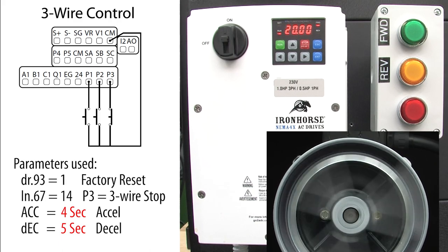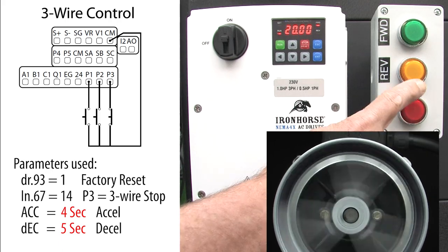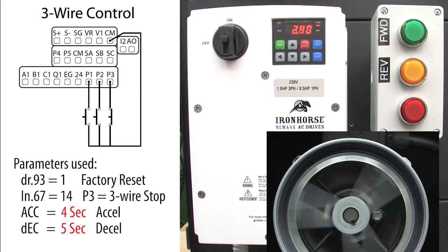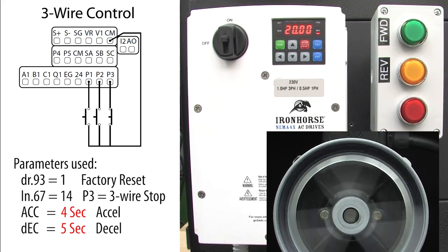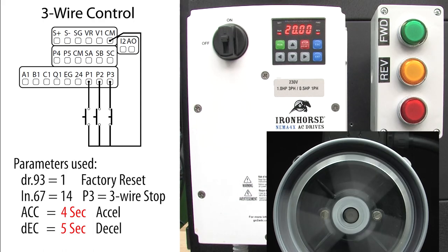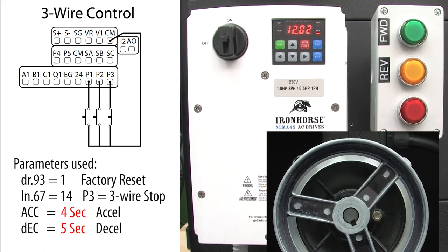Notice that I'm not holding the button down. Press the reverse push button and the drive automatically ramps down and ramps back up in the reverse direction. Perfect. And hit the stop button to stop.